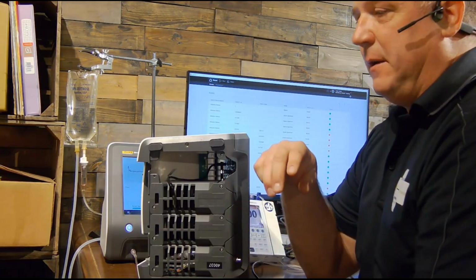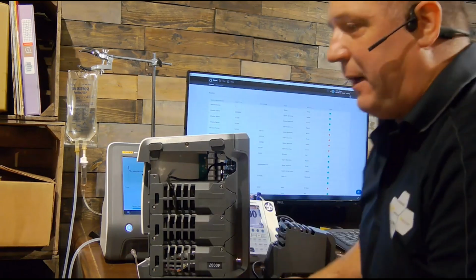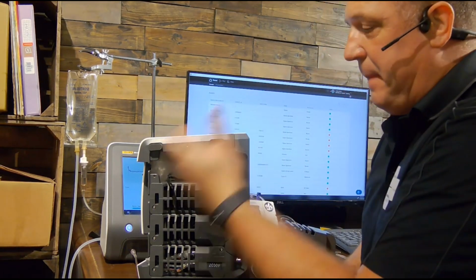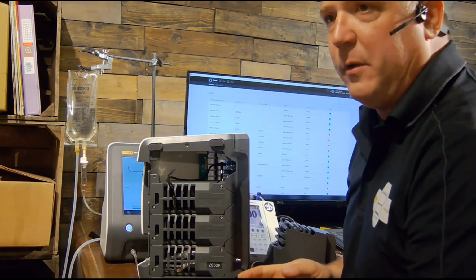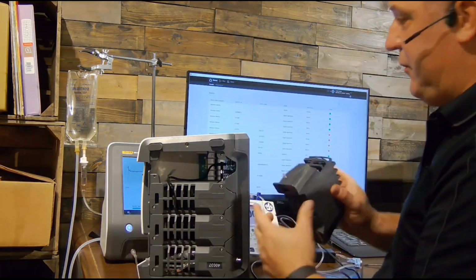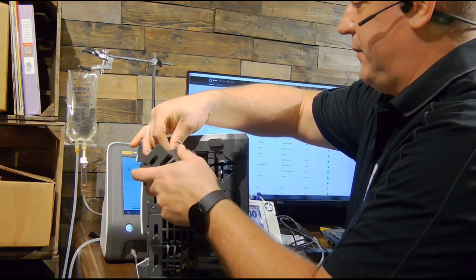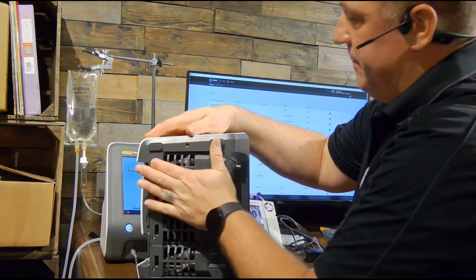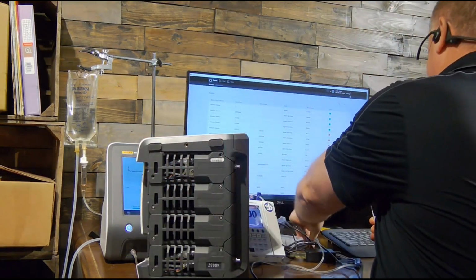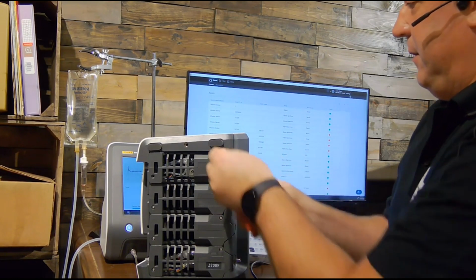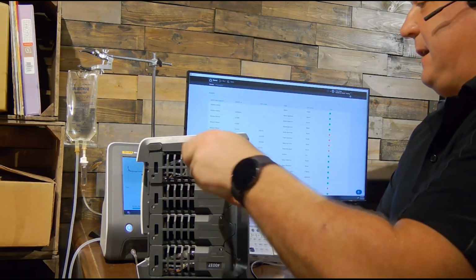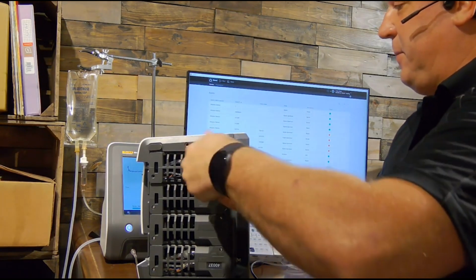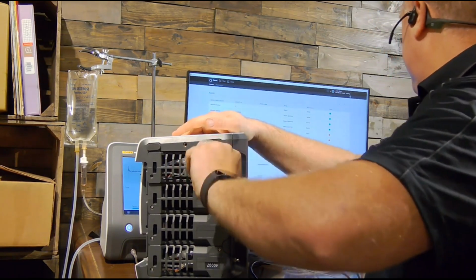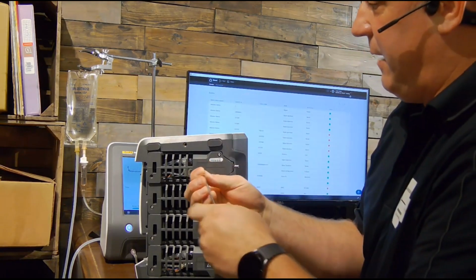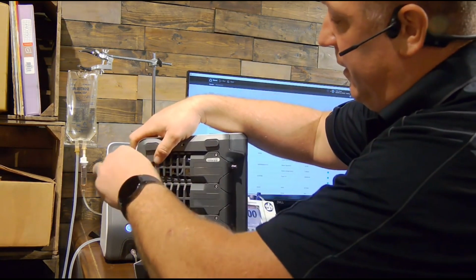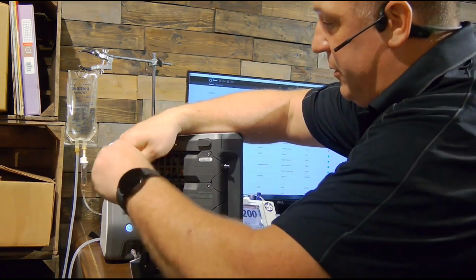So I could send this out. Maybe what I want to do is say I have a lot of these in my shop. I have shops that have 10,000 pumps. They buy a bunch of these, and then they go ahead and buy a few spare channels, or they buy 4 channels so they have some spares. I can simply take another channel, plug it back into the IDA-6, like so, slide it back in, insert my screw again, and my IDA-6 is ready to start testing infusion pumps. I never had any downtime. So a spare channel is pretty exciting because you don't lose that time while your IDA-6 is out of the shop. And again, if you have 10,000 IV pumps or even a few thousand IV pumps, you know that losing your IDA-6, your infusion pump analyzer, can be a real pill.